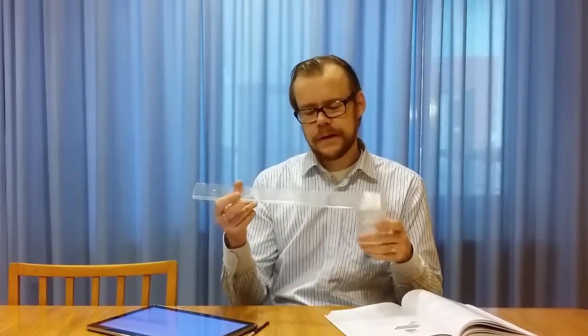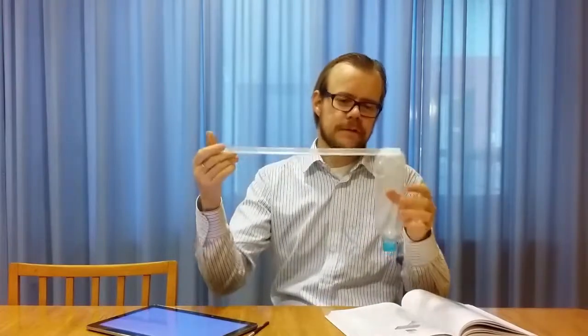You know that if you have a cantilever like this plastic piece here, you can design those so that you know the spring constant of it. You know what material it is made of, and you know the physical dimensions of it. And then you also know the spring constant of it and the force that is required to bend this. If you use that idea and design a very, very small tip, not as I have here, but made, for example, out of silicon with silicon technology, and in the demonstration I've showed you a few of those, then you can create a small tip with a known spring constant.